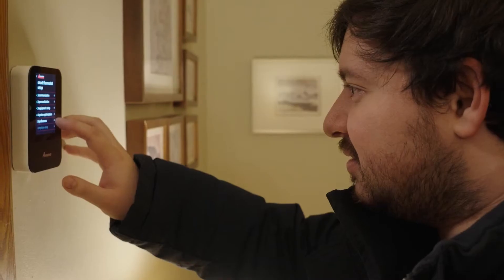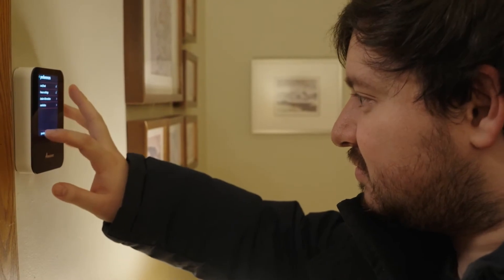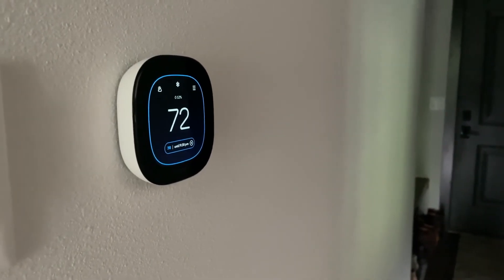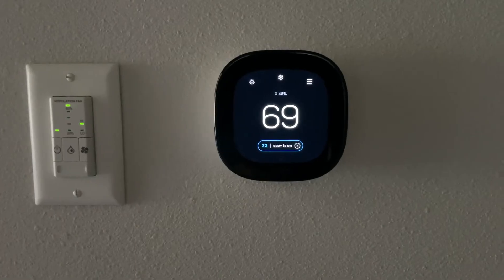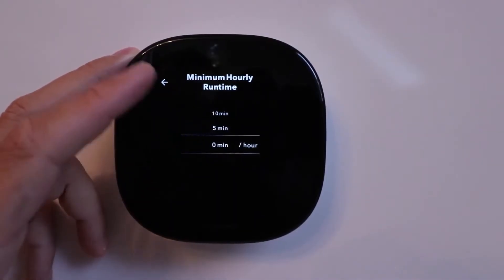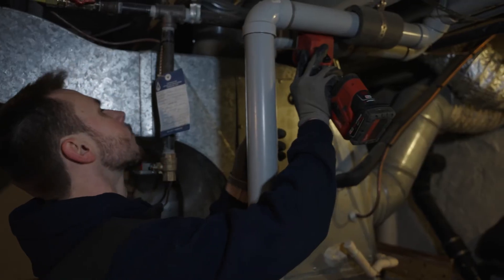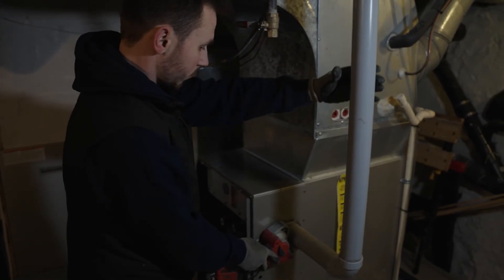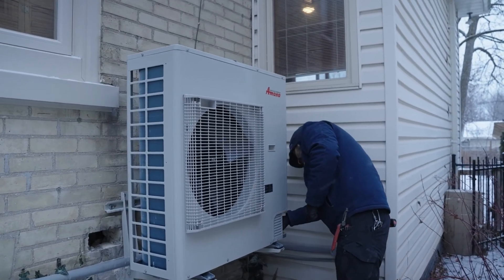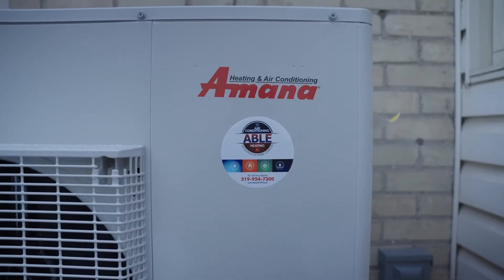The thermostat, control board, and heat pump must be in constant communication, adjusting in real time rather than just receiving basic on/off commands. A standard 24-volt system controlled by an ecobee thermostat operates using basic on/off signals and can only operate at two to four stages at most, meaning your heat pump is forced to run in large, inefficient jumps.